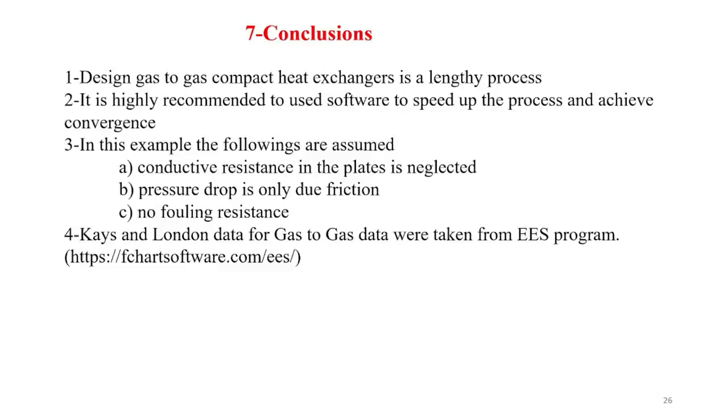In addition to all the parameters, like for example alpha and beta and hydraulic diameter and omega, which is the fin area divided by heat transfer area, all of them are tabulated in EES so that you can use them. What we did in the MATLAB program was take the tabulated data from EES and insert it into MATLAB, so that MATLAB now has the tabulated data of all the surfaces. So once you give the program the designation for that surface and the Reynolds number, you get all the properties that are needed in sizing a compact heat exchanger.